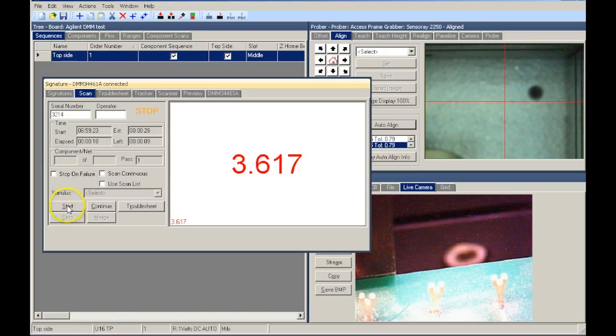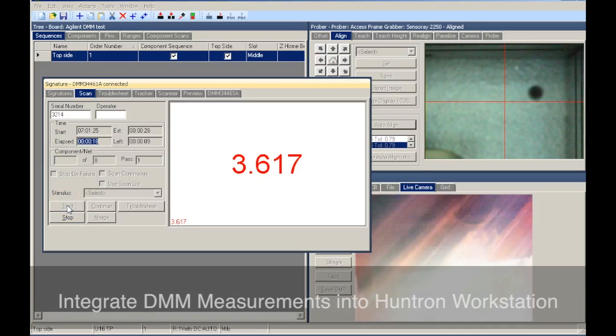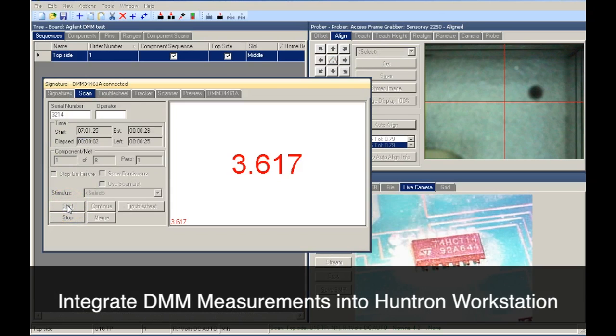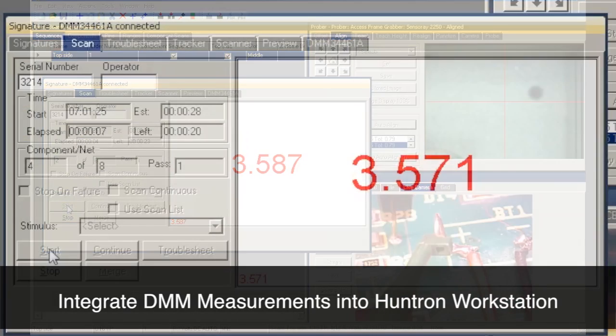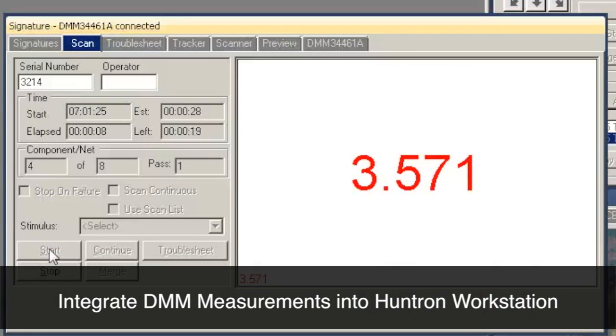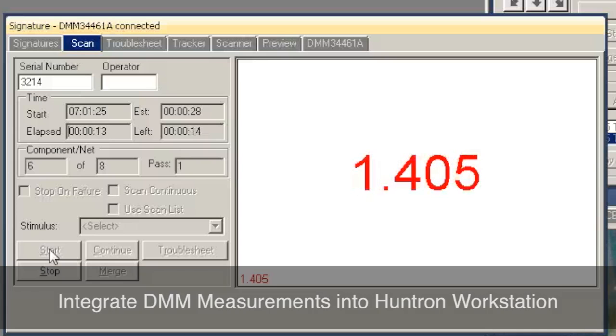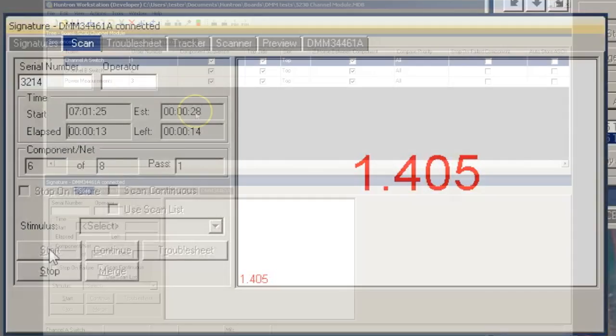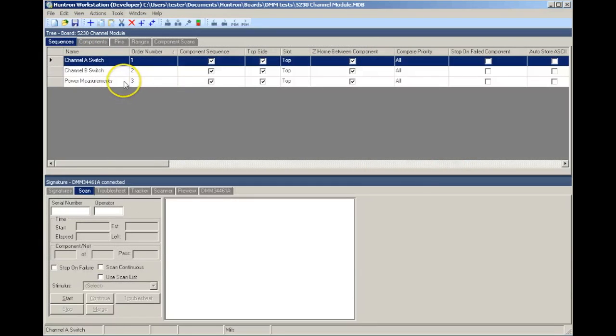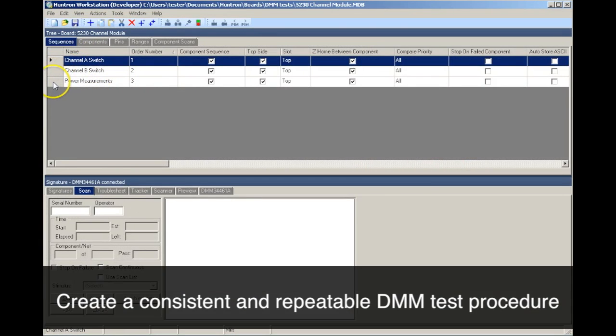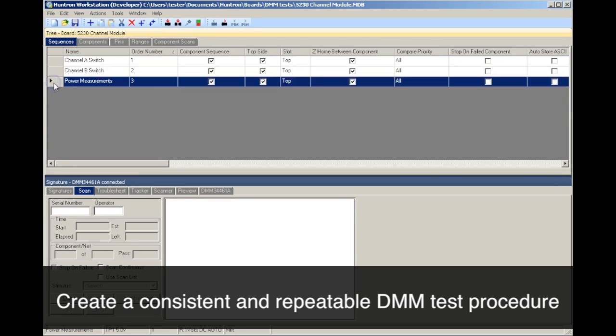Using Huntron Workstation, you can create a specific test procedure, take measurements with your DMM from a known good assembly, store those measurements to a database, and compare to them when measuring a suspect assembly. This makes it possible to create and follow a set test procedure allowing for consistent and repeatable troubleshooting.